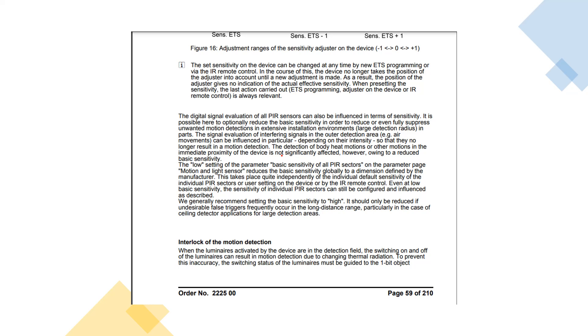Specifically in the off state — when the light is on and then goes off — previously there was heat emitting from that light and when the light turns off that heat disappears. The PIR actually detects heat, so this slight change in heat may result in triggering the PIR again. The PIR thinks there is movement and turns back on — that's why this motion and light interlock sensor setting exists.